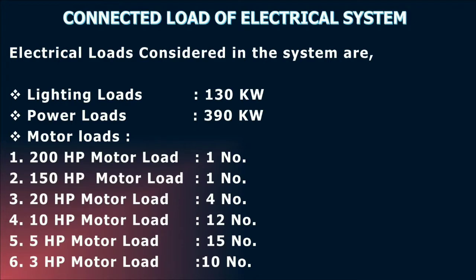Now, in order to explain the selection of supply voltage and the selection of transformer rating, I am considering an electrical system with the following loads. I have considered lighting loads to be 130 kW, power load to be 390 kW, and motor loads of 200 HP 1 number, 150 HP 1 number, 20 HP 4 numbers, 10 HP 12 numbers, 5 HP 15 numbers, and 3 HP 10 numbers.